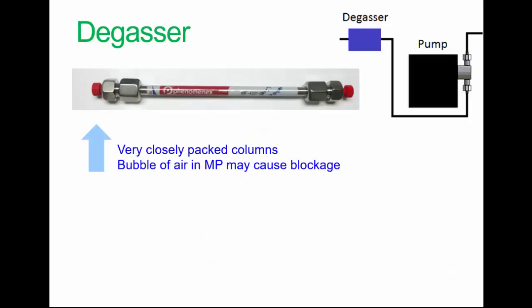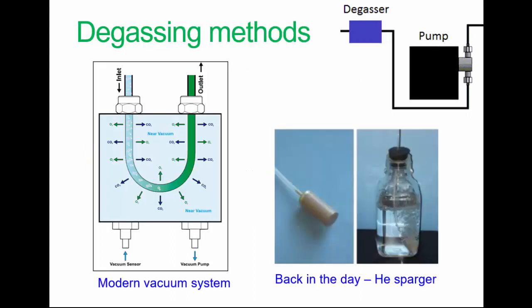So the degasser, going back to the schematic diagram. If the mobile phase contains any dissolved gases, they may form a bubble, which under the high pressures involved may block the column. A degasser is a vacuum system that removes any dissolved gases.